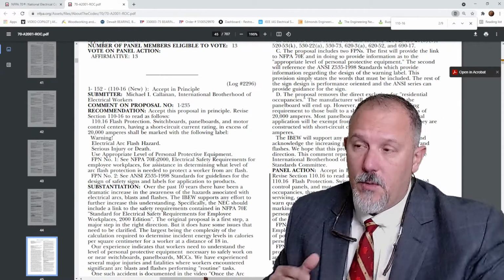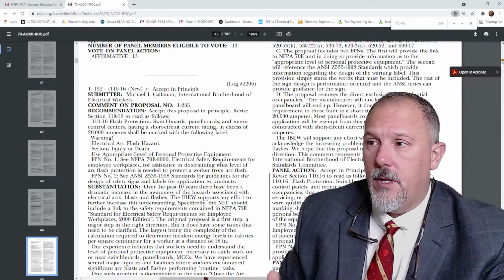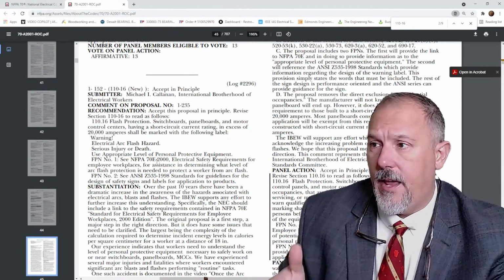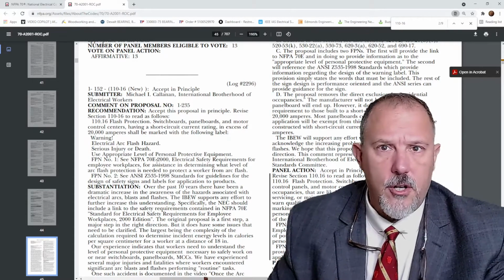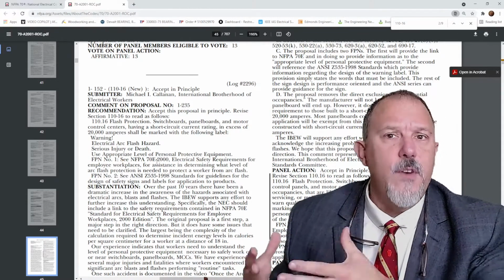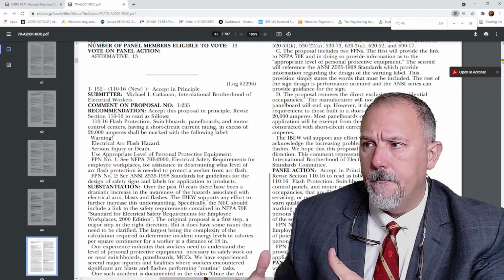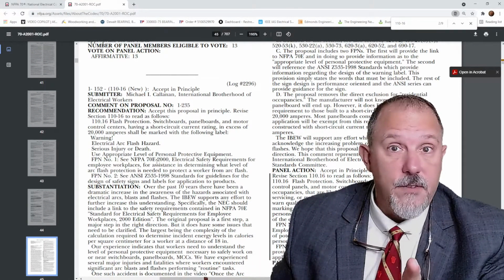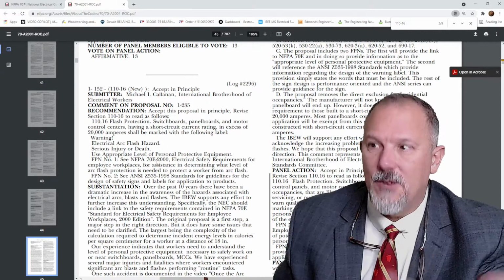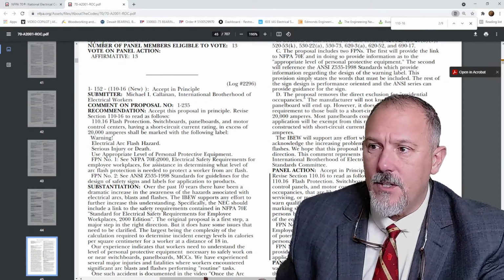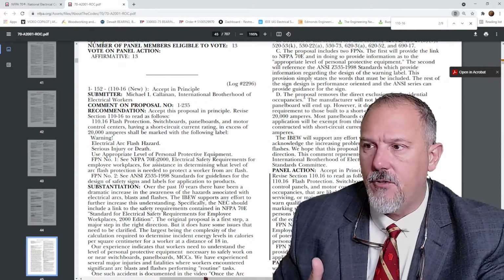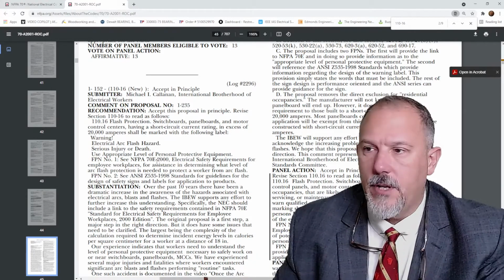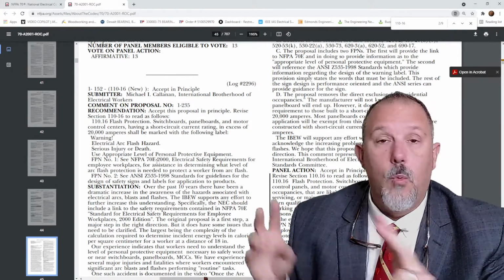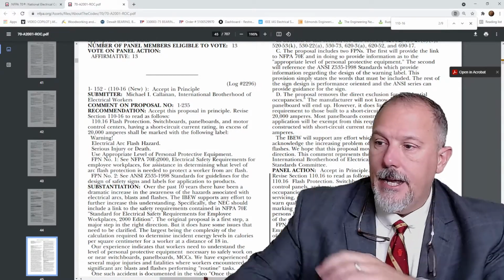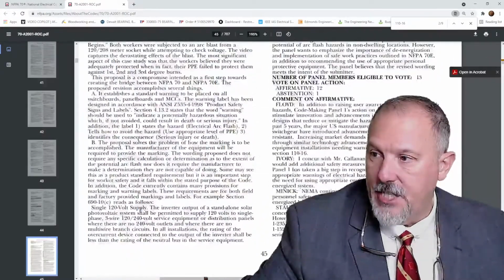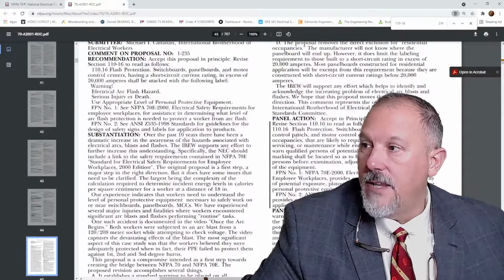So what Michael was going after, what the IBEW was promoting, was saying, look, if it is greater than 20,000 amp short circuit current rating, meaning you've got a lot of available fault current at that service entrance equipment, or no, not at service entrance equipment, just at a switchboard, panel board, or motor control center. So you have a significant amount of fault current. They were looking at a label that just said warning, electrical arc flash hazard. And you can read through their substantiation, and you can look at the panel action.